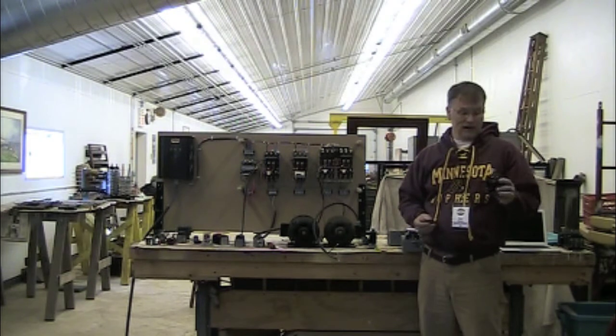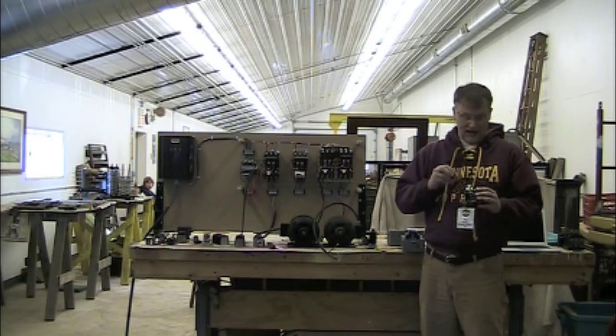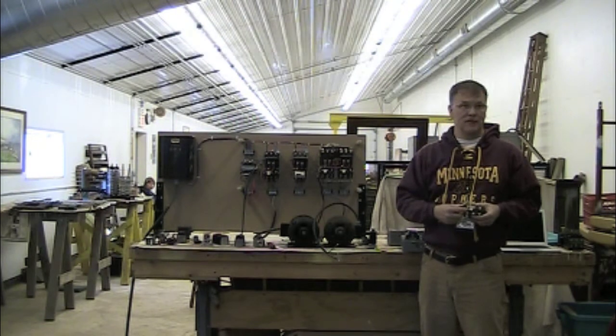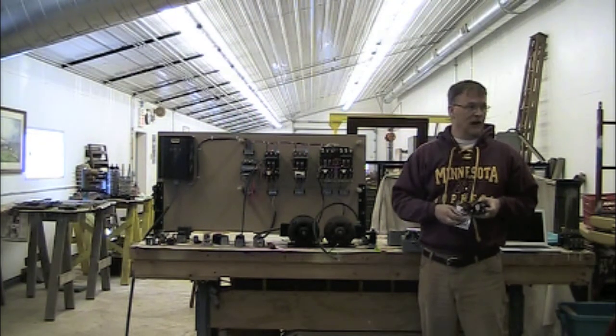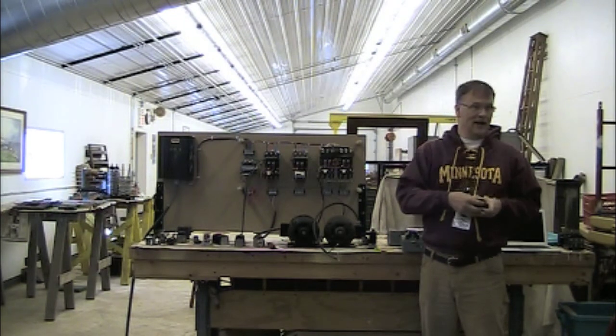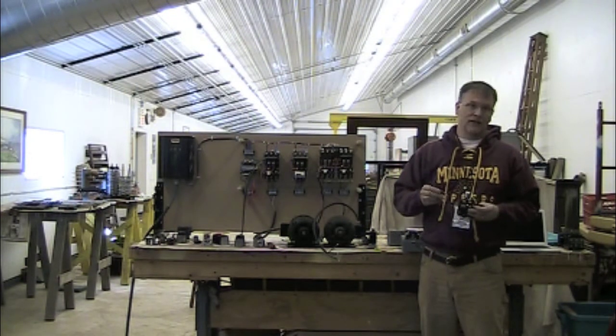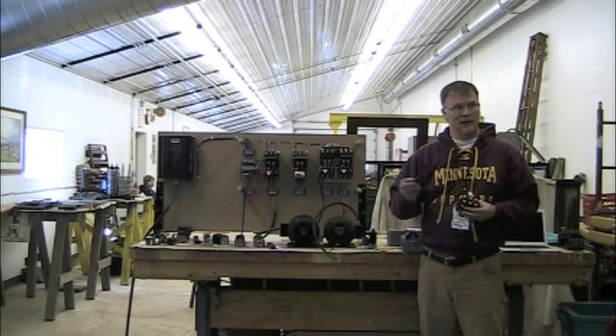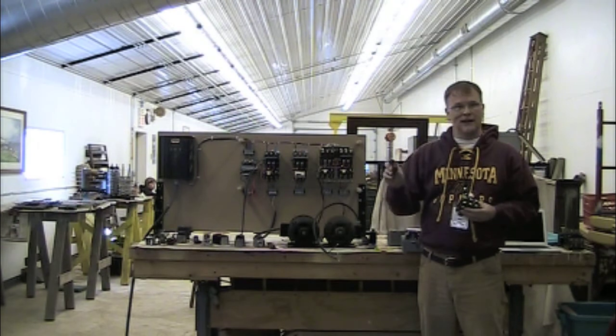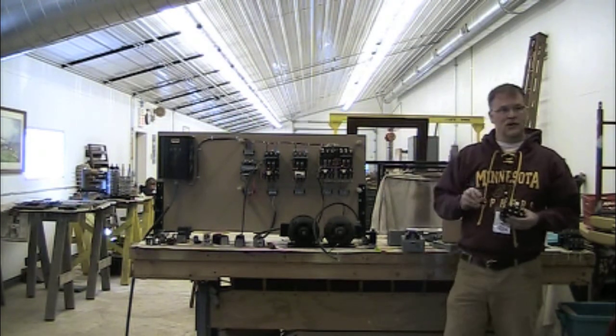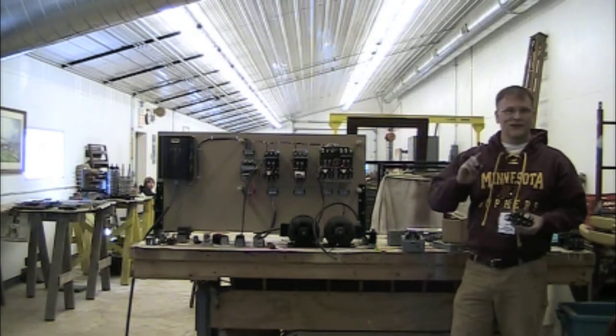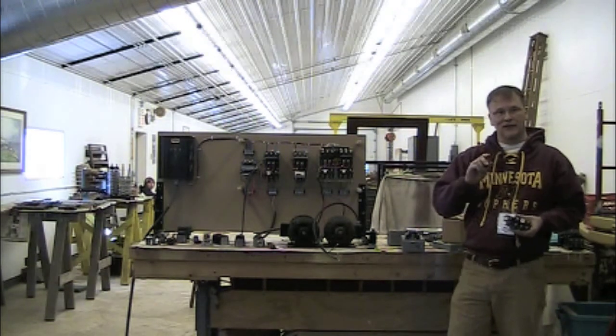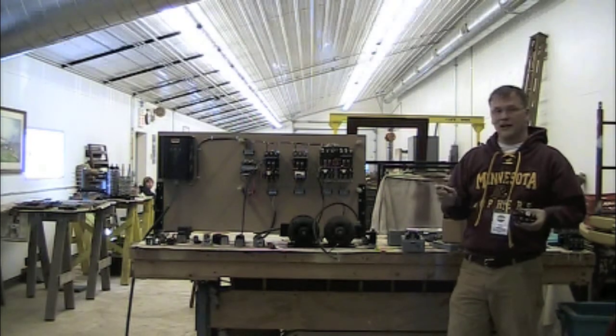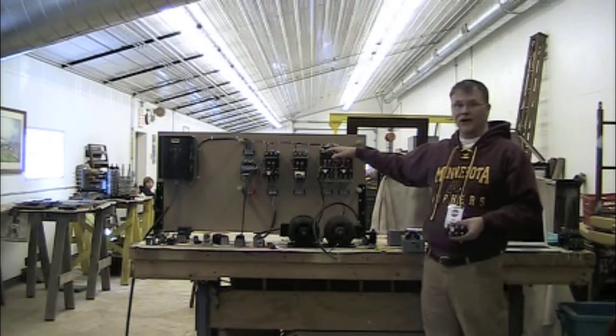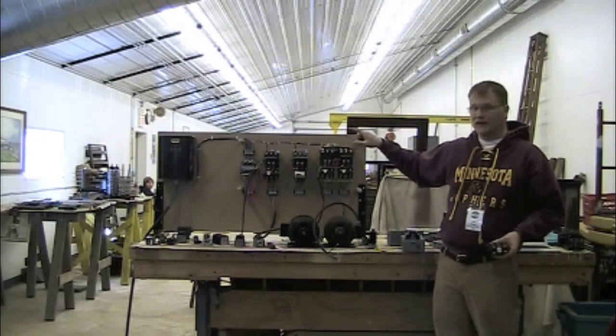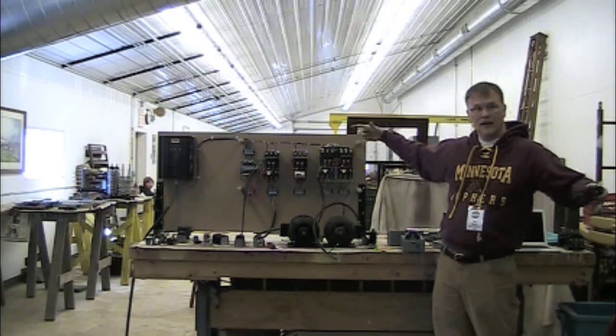And then on the later ones, like on the 509s, they're designed so that you can't jumper these or defeat them in any way, because there are little ratchet pawls down in there, and all of the positions have to be occupied. And in Allen Bradley, if you look at their heater charts, they never really seem to make much sense. It's very nonlinear, but all of the values that they show for current are pretty much empirically derived values, and they're all for a specific set of conditions. So there may be one set of heater charts for the scenario where you've got a bunch of starters and a control thing. This is an open configuration, so it's open to the air.